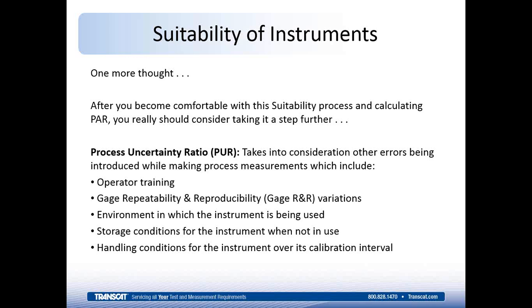All right, so an active measurement assurance program has to not only consider the right tool for the job, but the regular calibration, and is that calibration performed correctly? Does it support the process where the instrument's used? Does the calibration include the correct tolerances of the instrument? Sometimes that can come into play as a factor. And the calibration has to be valid. In other words, the calibration measurement uncertainty has to support the measurements being made.